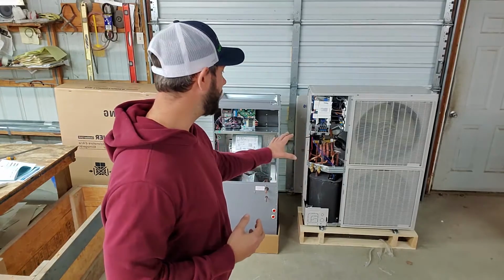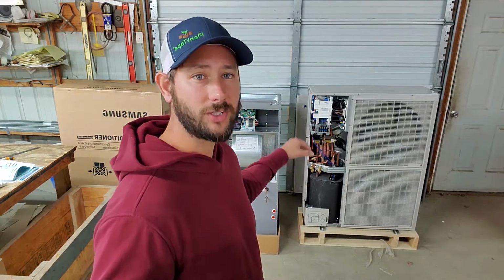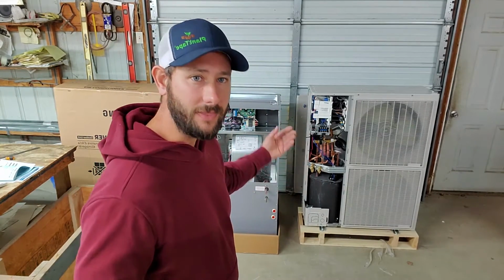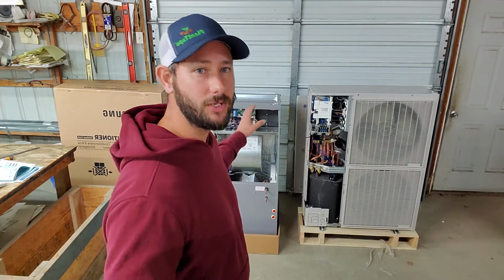Now during cooling mode, the outdoor unit is actually going to wait the 3 minutes, and then it'll come on. The indoor fan blows, but during heating, it's the opposite. The indoor fan does not come on, the outdoor unit comes on, and then it begins to build heat. Okay, so I think that is super efficient, especially when it's really, really cold outside. You don't need cold drafts in your home. You need good warm heat.